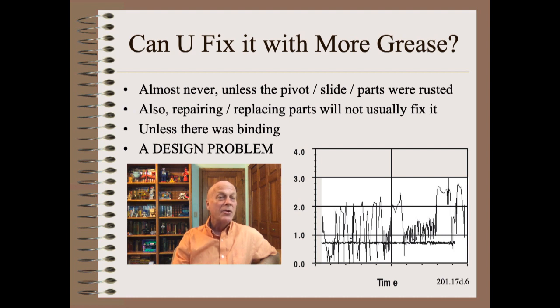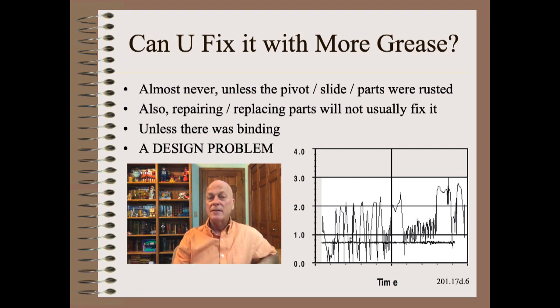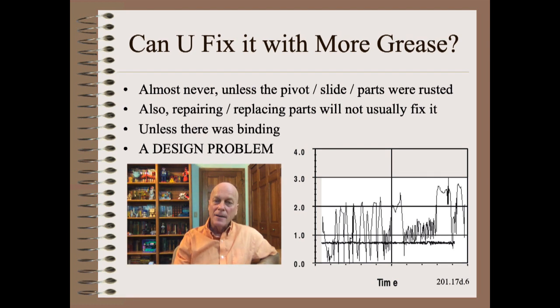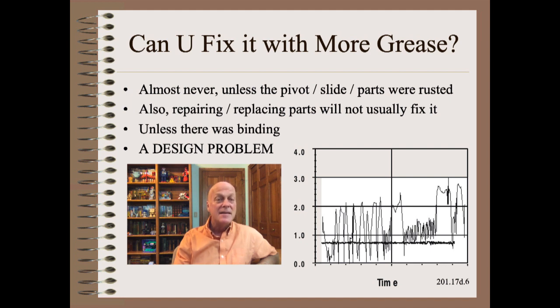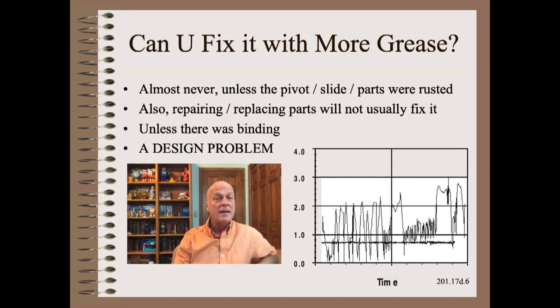Some of you are probably wondering: can I fix the friction by adding more grease? The answer is almost never, unless the pivot, slide, or part were rusted. Also, repairing or replacing parts will not usually fix it, unless there was some noticeable binding such as due to severe misalignment. The reason that you seldom can fix this problem in the field is because this is a design problem, not a maintenance or operation problem, at least in most cases.